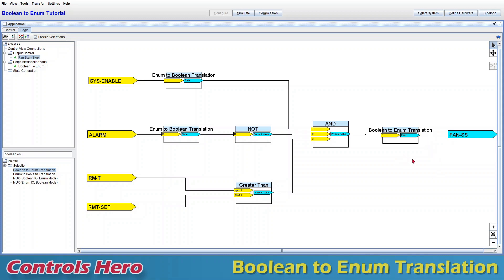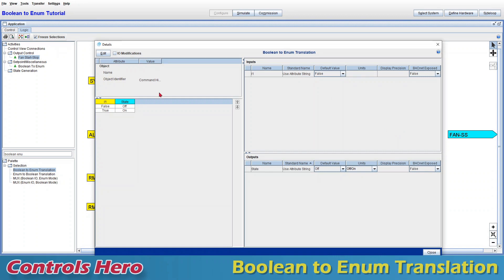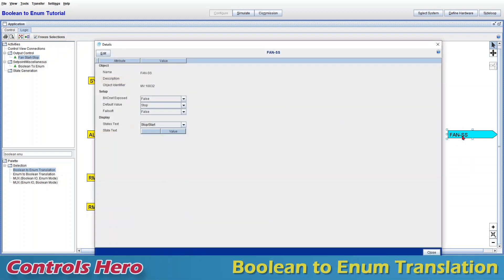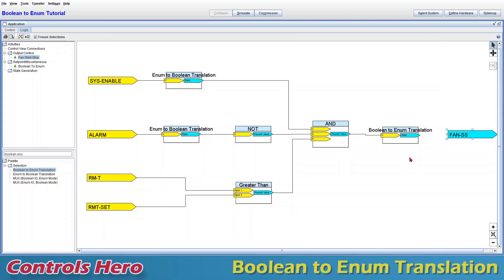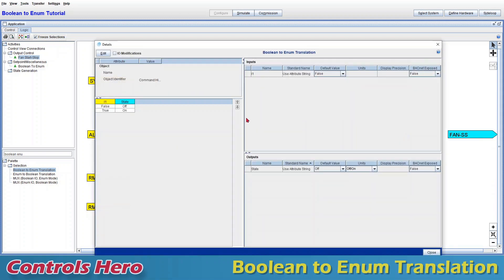Here is where units need to match. By default, when you create a boolean to enum translation, the input is false and true — boolean — which is correct. But the enum output side defaults to off/on. Enum can have many different units, and if you recall, our fan start/stop uses units of stop/start, so we have to match those units.